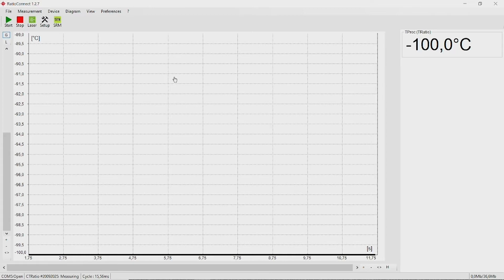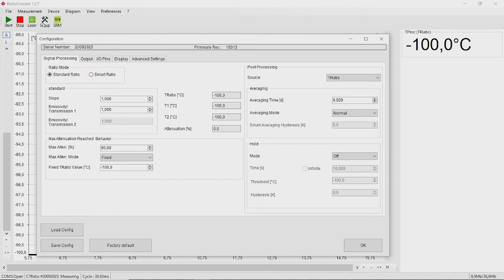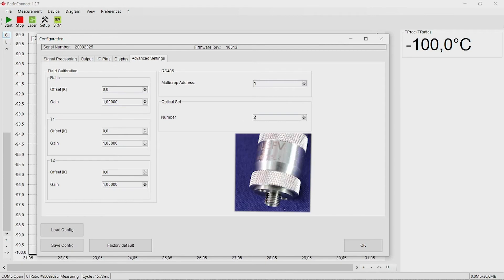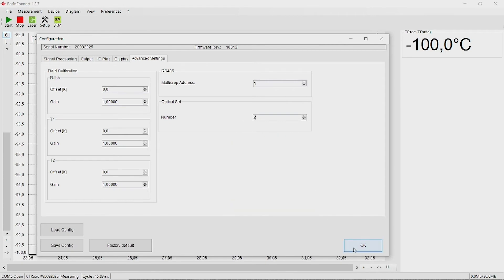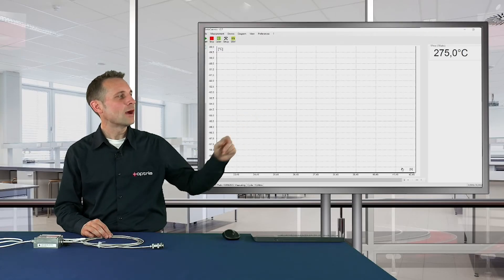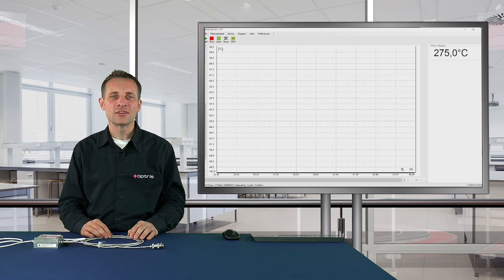To set the right number for the fiber cable, go to the menu Setup and to the tab Advanced Settings. Here at this position, you can change the Optical Set number. In my case, I have the number 2. Click on OK. You can see now on the screen on the right side the correct temperature of 275 degrees C.